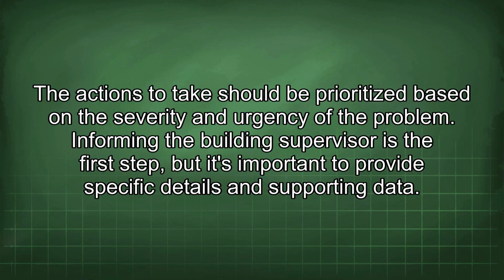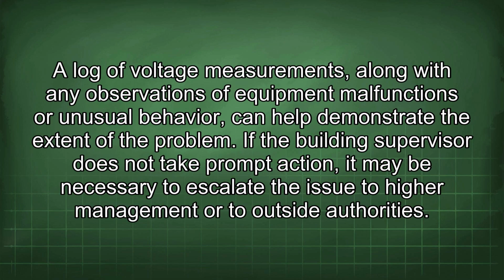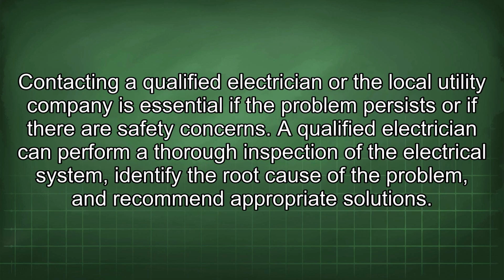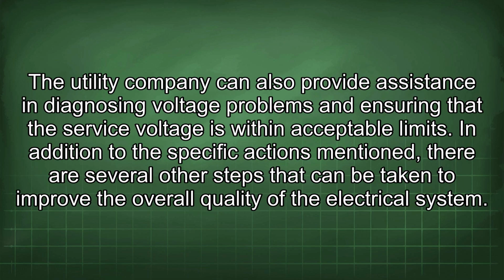Informing the building supervisor is the first step, but it's important to provide specific details and supporting data. A log of voltage measurements, along with any observations of equipment malfunctions or unusual behavior, can help demonstrate the extent of the problem. If the building supervisor does not take prompt action, it may be necessary to escalate the issue to higher management or to outside authorities. Contacting a qualified electrician or the local utility company is essential if the problem persists or if there are safety concerns. A qualified electrician can perform a thorough inspection of the electrical system, identify the root cause of the problem, and recommend appropriate solutions. The utility company can also provide assistance in diagnosing voltage problems and ensuring that the service voltage is within acceptable limits.